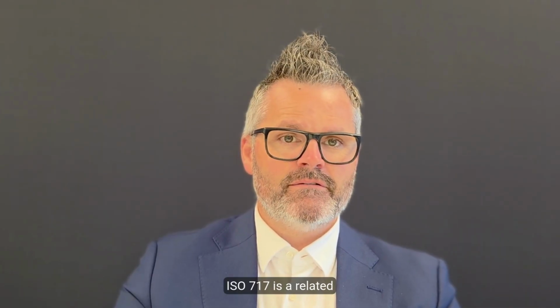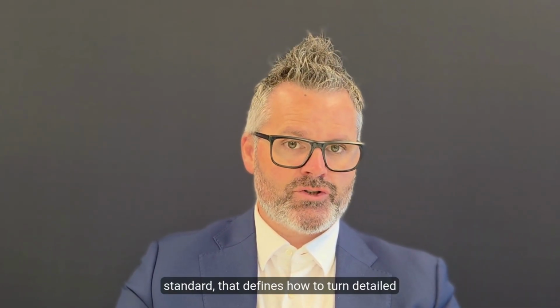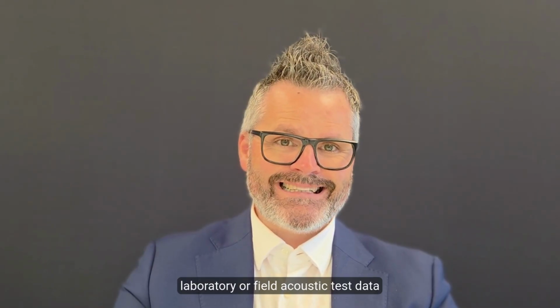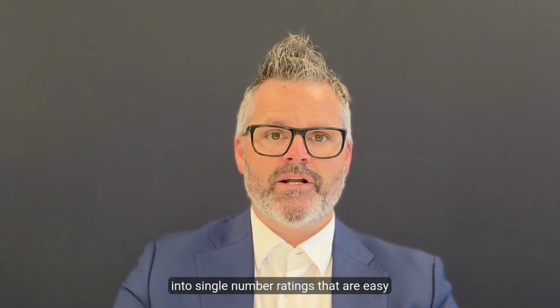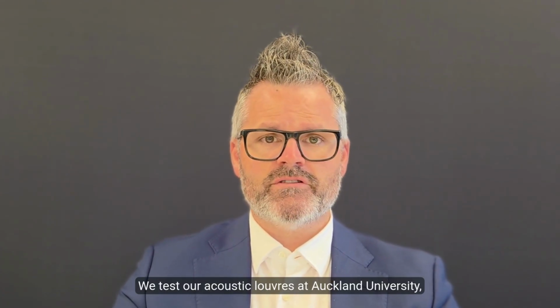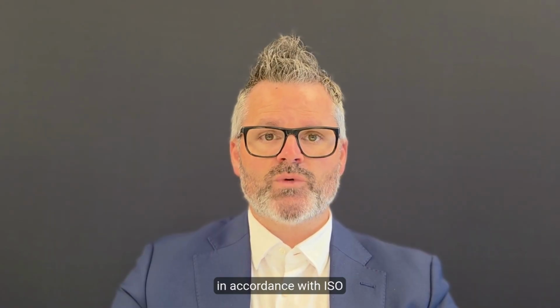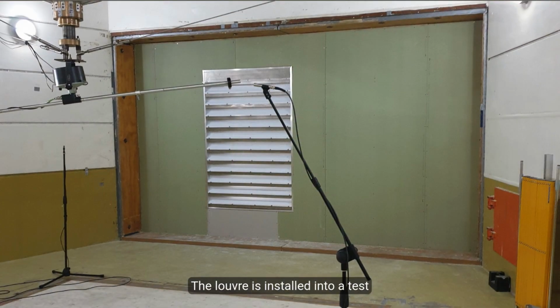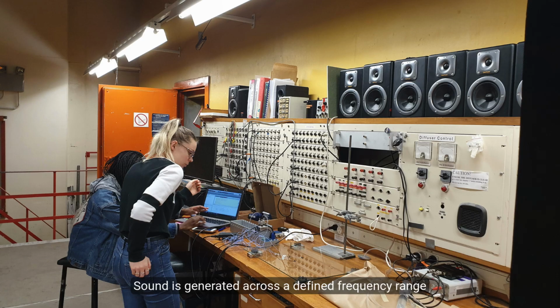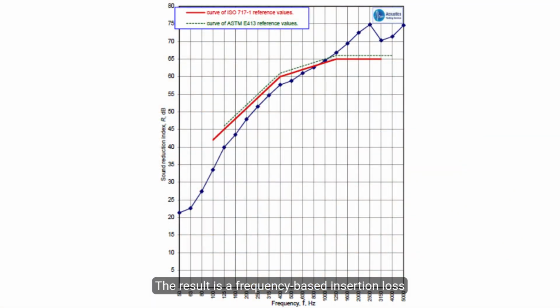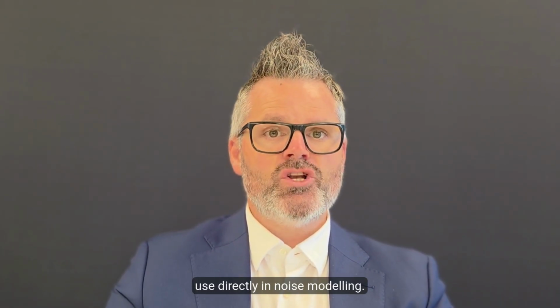ISO 717 is a related standard that defines how to turn detailed laboratory or field acoustic test data into single number ratings that are easy to compare and specify. We test our acoustic louvers at Auckland University in accordance with ISO 10140-2. The louver is installed into a test aperture between a source room and a receiving room. Sound is generated across a defined frequency range, and the reduction achieved by the louver is measured. The result is a frequency-based insertion loss curve that acoustic engineers can use directly in noise modelling.